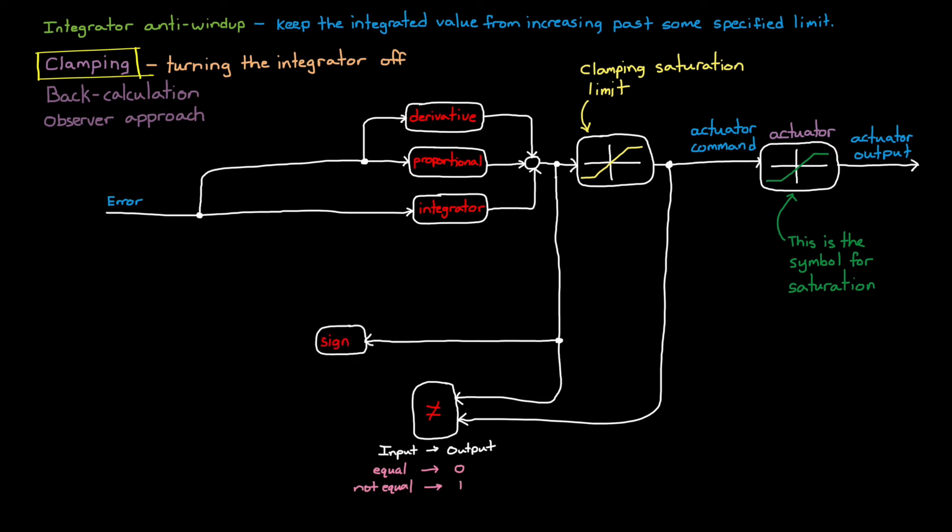The second check is to compare the sign of the controller output with the sign of the error. If both the error and the controller output are positive, then we know that the integrator is still adding to the output to make it more positive. And if they're both negative, then we know that the integrator is trying to make it more negative. So we're looking to see if the output is currently saturating and the integrator is attempting to make things worse. From this we can tell whether to clamp or not to clamp.